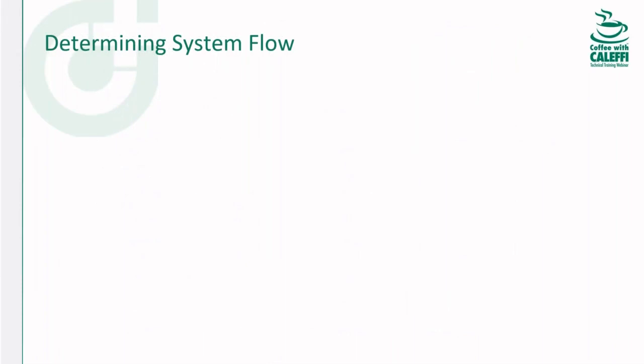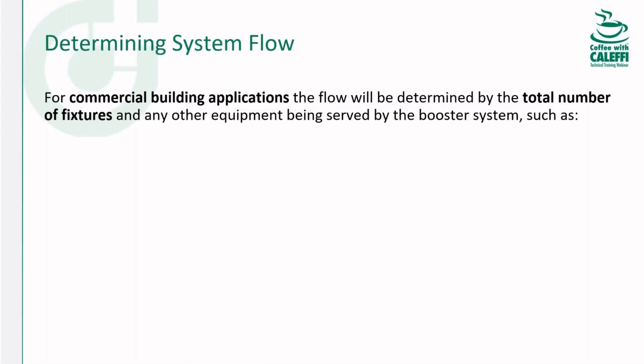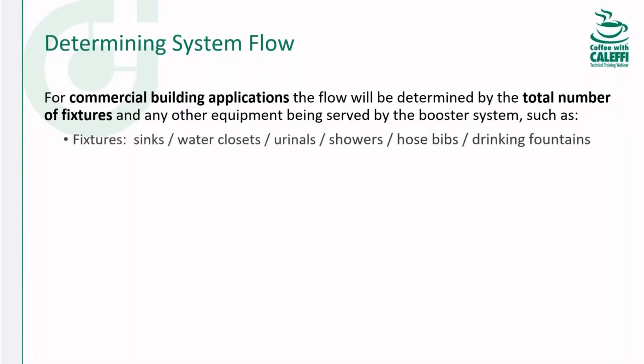Okay, so system flow. Reece, do you want to take this one? Sure. So especially for commercial buildings, and it might be an office building, a mixed use building, an apartment building, the flow is determined by, obviously we're going to count the fixtures, right? But what we're not going to do is add up the fixture flow rates. So, oh, this is a shower head, it takes 2 gallons a minute. This is a 25 gallon a minute flush valve. You're not going to add all those up cumulatively.